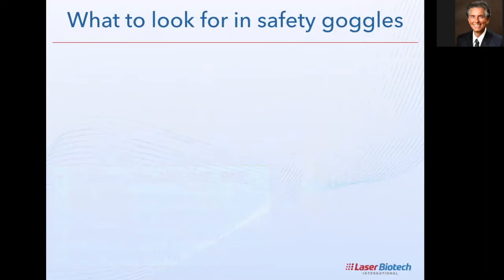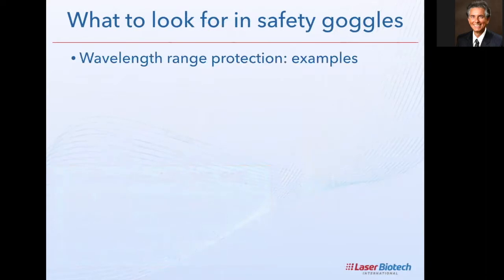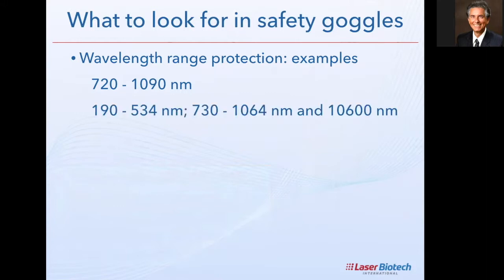Let me show you the wavelength range we need to worry about. Safety goggles may specify a range — for example, 720 to 1090 nanometers — meaning any laser with wavelengths falling in that interval is covered. Another example shows multiple ranges, such as 190 to 534 nm with a rating number, then skipping to 730 nm and above. You have to be careful about gaps — make sure the intervals listed on your safety goggles cover all the wavelengths your laser uses.